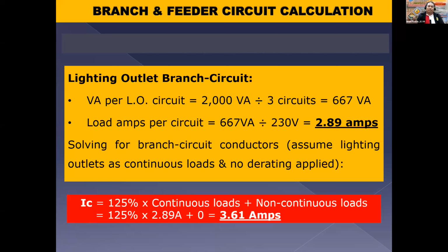Okay? So ang calculation ko dito, wala akong inapply na derating muna, ha. It's considered na standard yung installation natin na not more than 3 conductors in a raceway at yung ambient natin is relatively nasa standard ambient temperature of 30 degrees, no? But anyway, kung certain conditions dictate na mag-derate tayo, like for example, more than 4 conductors yung pinahatak mo sa installation, then apply the appropriate derating factor. Meron tayong table dyan sa PEC din, no? So ito is assume lang na walang derating applied, okay?